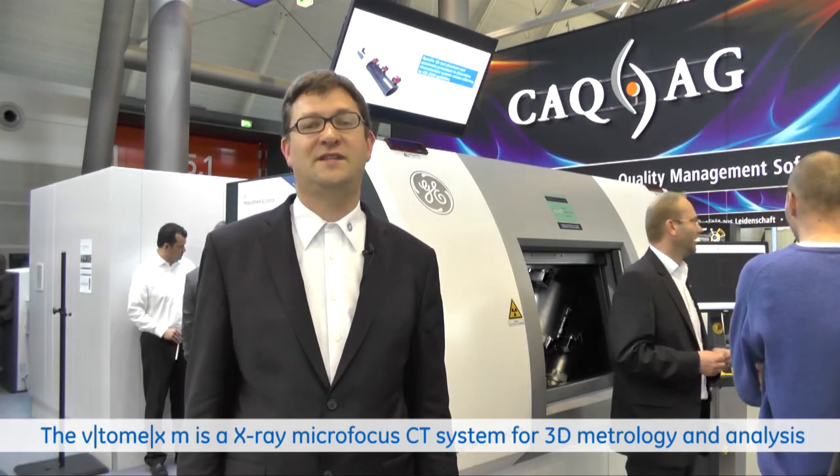The next system I would like to introduce is the v|tome|x m Metrology Edition. It combines high-performance 3D imaging with high-precision metrology. It is specified according to VDI 2630 with an accuracy of down to 4 micrometers. It is also the first micro CT system which we offer with ScatterCorrect technology.